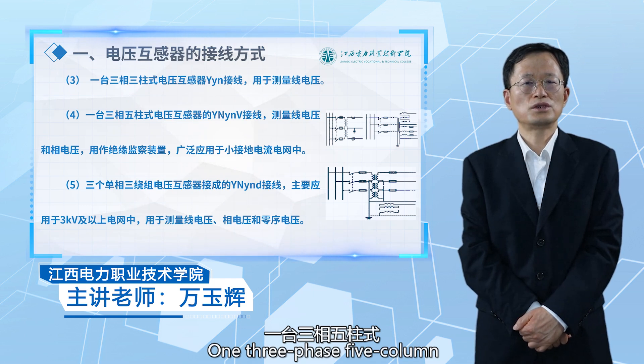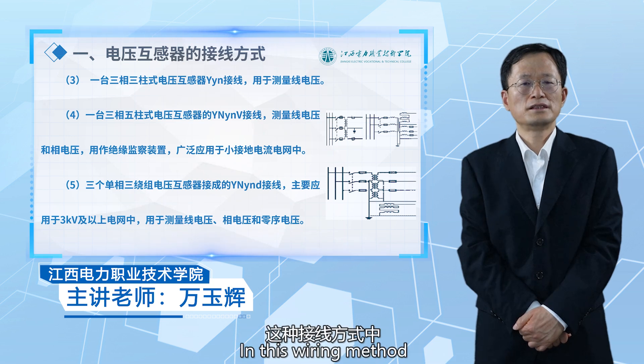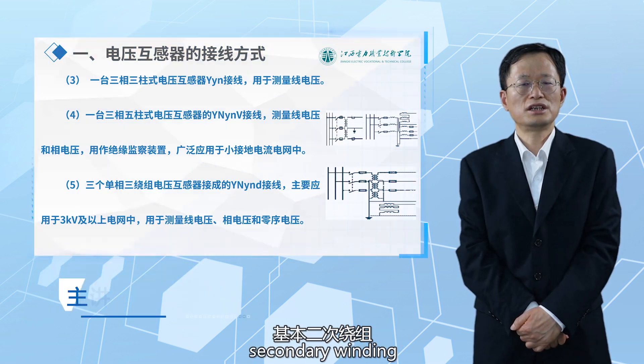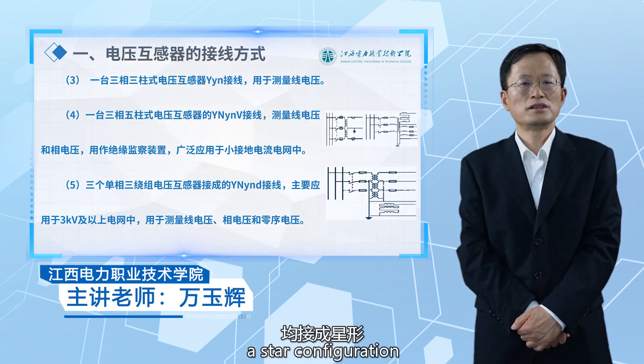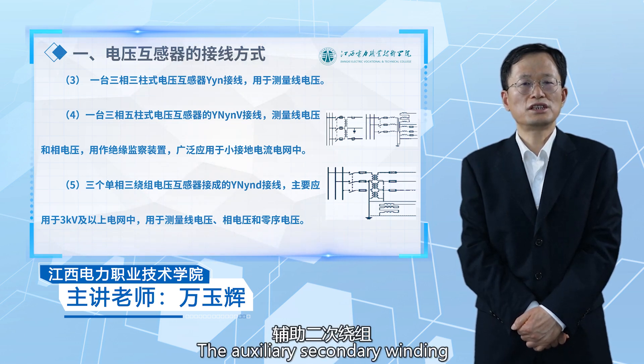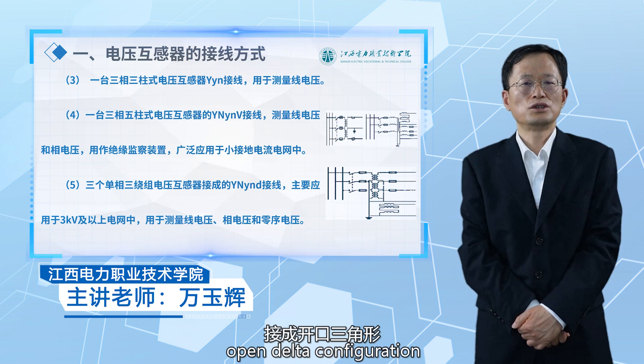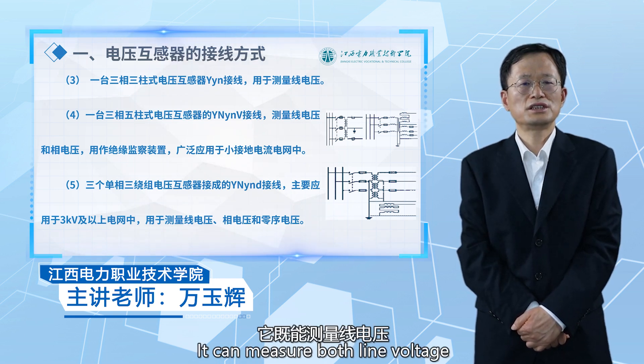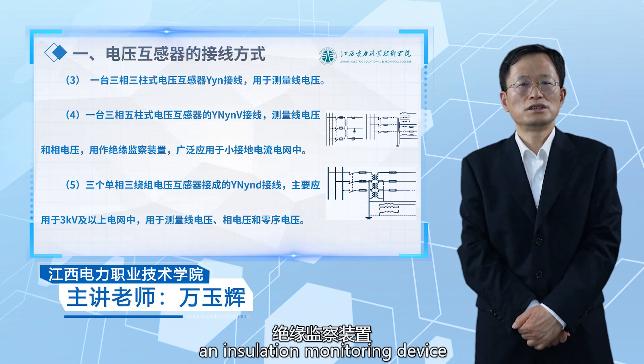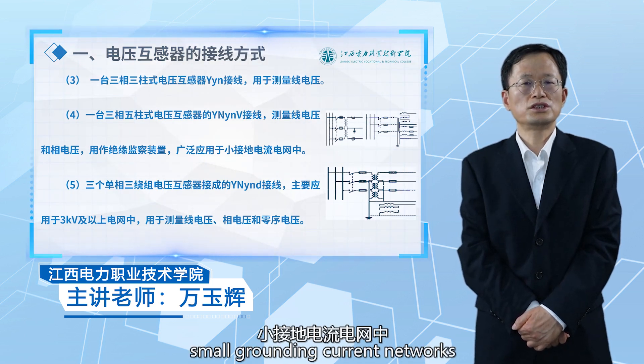One three-phase five-column voltage transformer YNynV wiring: the primary winding and basic secondary winding are connected in a star configuration with the neutral point grounded. The auxiliary secondary winding is connected in an open delta configuration. It can measure both line voltage and phase voltage, and can also be used as an insulation monitoring device, widely used in small grounding current networks.